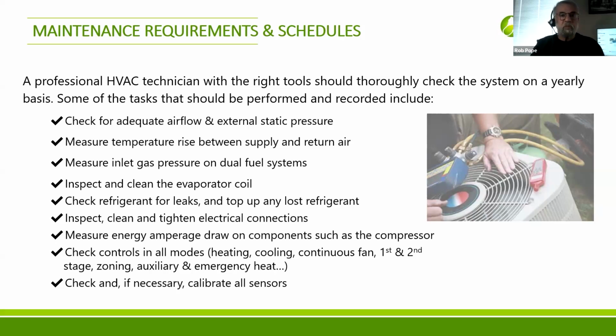You might discover where that thermostat is on a wall. In some cases, the sensor's built right in. In some cases, it might be impacted by something nearby. It's always maybe a degree or two off, right? So you want to calibrate it, reset it, if you find that. Or the outdoor temperature sensor might be in a place that gets too much sunshine, so it's not sensing the ambient temperature where you need it, in the shade, ideally. Or there might be something nearby, maybe a dryer vent too close by coming on and then impacting what it's sensing. Anything like that, you just want to make sure that the sensors are actually reading the right temperatures.